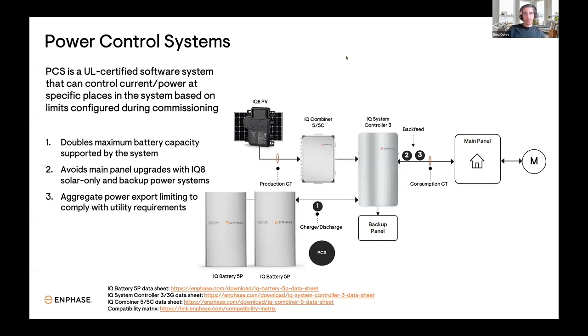Zoom tricked me. Okay, so here you can see a system that's using PCS, and it's a partial home backup. So we have the main service panel that has some loads in it, and the backup panel, which has the backed up loads. Now, because the function of PCS is to ensure that there's a limit to how much current can backfeed to the main service panel, that's done with consumption CTs installed between the controller and the service panel.